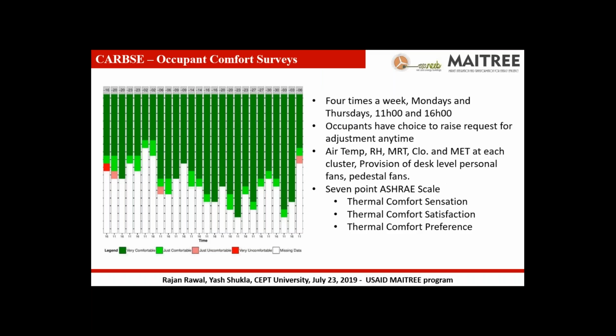A few other slides I want to talk about. While we have only talked about energy consumption in the earlier slides, it's very important to understand occupant comfort. Finally, I can turn off the air conditioning system and show 0 kilowatt hour per meter square, but are the occupants comfortable in the space or not? That's why it's very important to keep track of that. So we take surveys twice a week, on Mondays and Thursdays, at 11 o'clock and 4 o'clock in the afternoon, asking occupants how comfortable they are. They have a choice to adjust the set points. We also note the temperature, relative humidity, mean radiant temperature, the clothing occupants are wearing, and their activity level, or met. Have they been working on research equipment, or sitting and working in the lab? There are also personal fans and pedestal fans that we have provided for the occupants to adjust their local environment, which gives us more flexibility to adjust the ambient temperature.